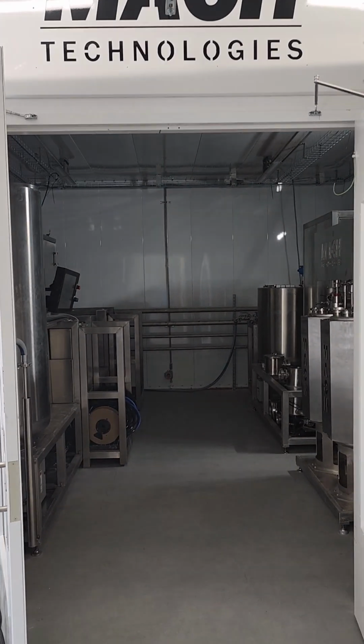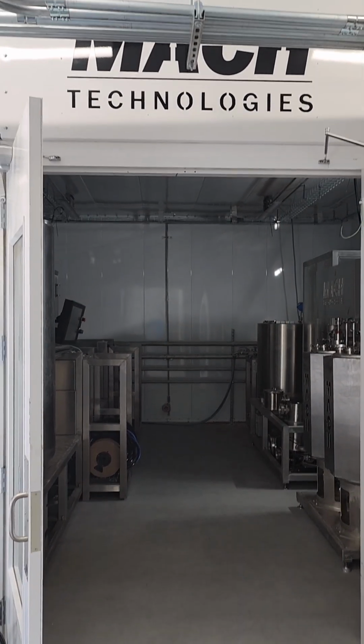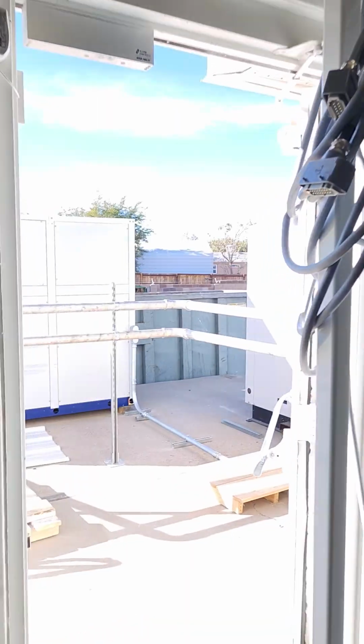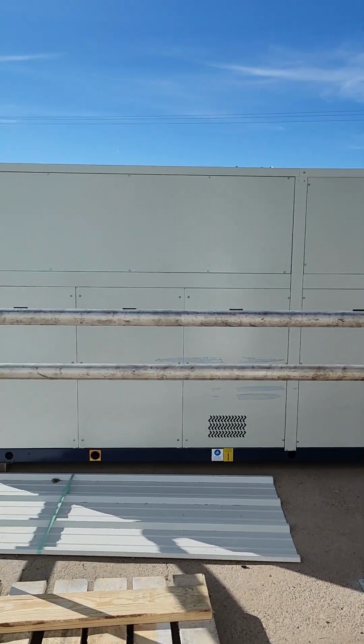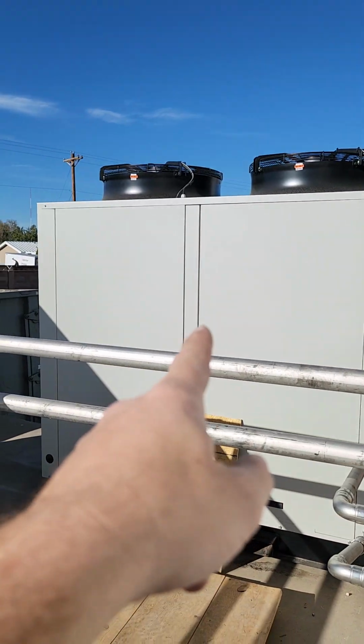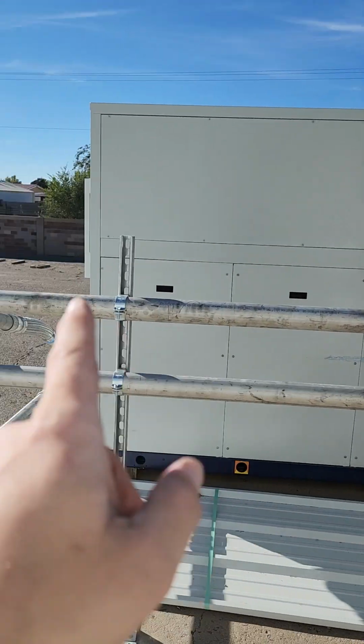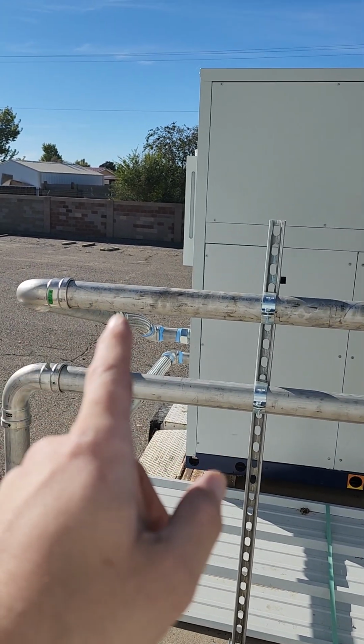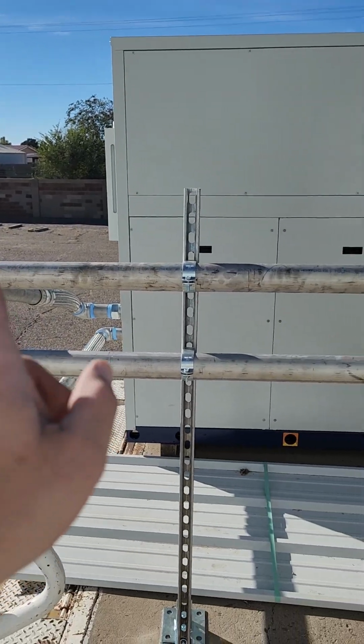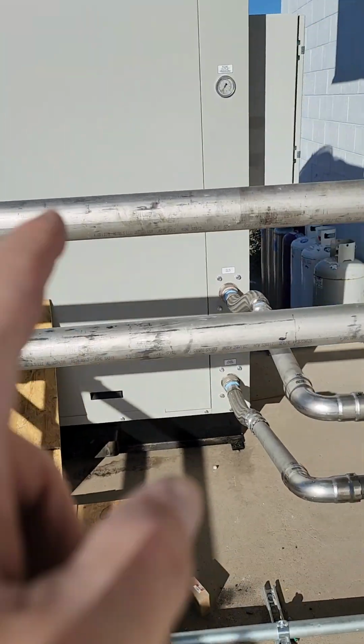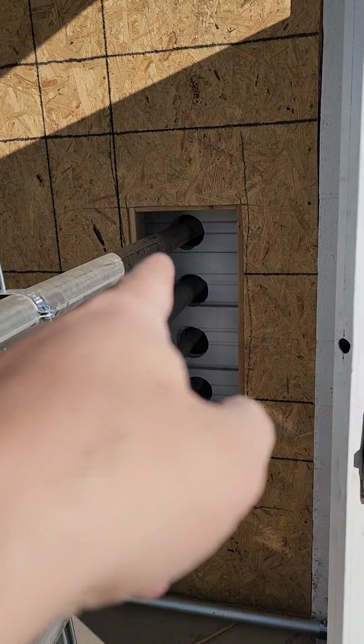About 3 weeks ago, we shipped down and installed the C1D2 room, plus two of our chillers that are outside, so we set these in place — the ultra-low temp one, which is this one, and our low temp chiller. Their local on-site MEP handled all the process piping from both chillers into the booth and into the building.